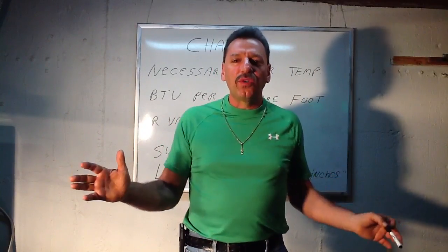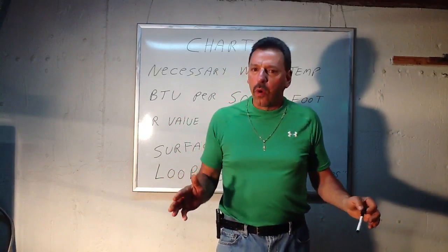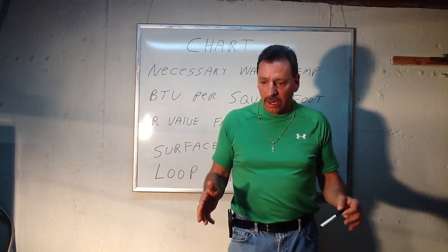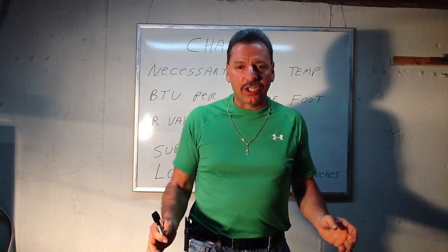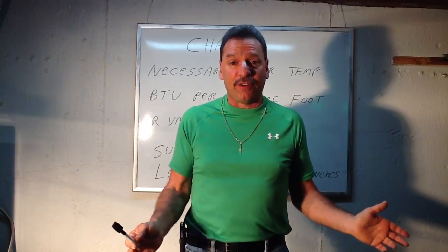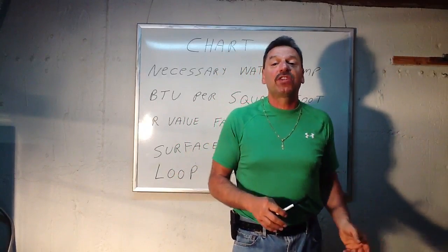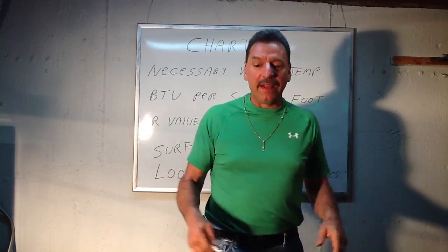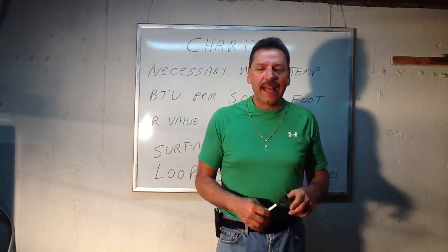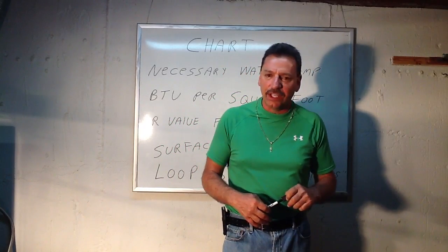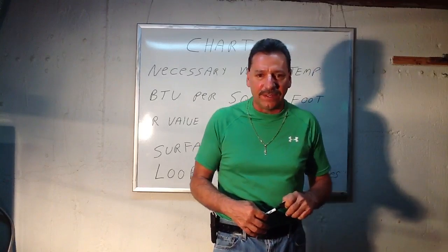The more zones with radiant heat, the way, way better off you are, the way more happy you're going to be, the way more comfortable the house is going to be. Yeah, it's more expensive at first, but long term it's going to matter. Everybody that puts tubes under the whole house and puts one thermostat, that's never, ever going to work. It just isn't going to work, no matter what you do.